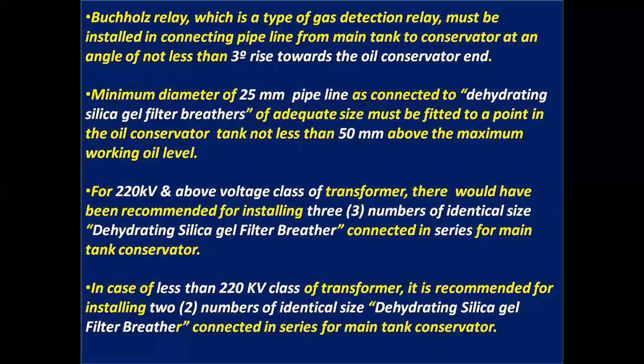Buchholz relay, which is a type of gas detection relay, must be installed in connecting pipeline from main tank to conservator at an angle of not less than 3 degree rise towards the oil conservator end. Minimum diameter of 25 millimeter pipeline as connected to dehydrating silica gel filter breathers of adequate size must be fitted to a point in the oil conservator tank not less than 50 millimeter above the maximum working oil level.